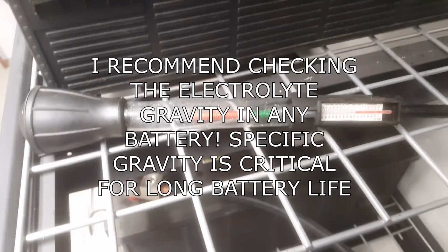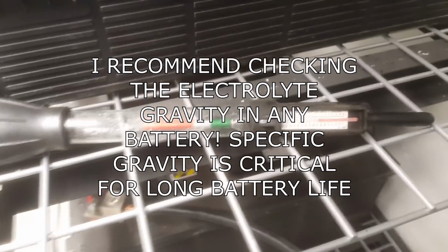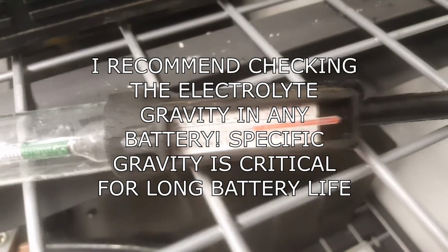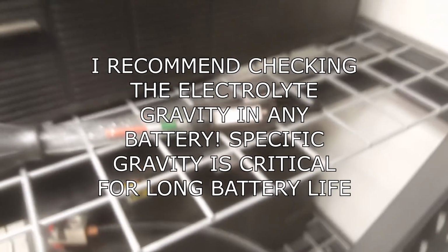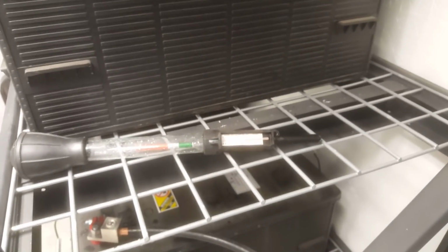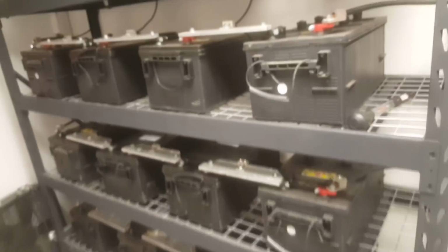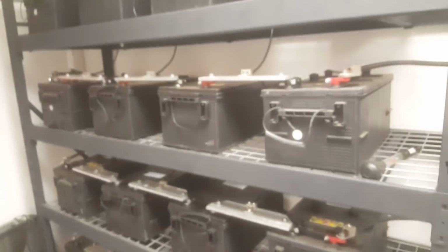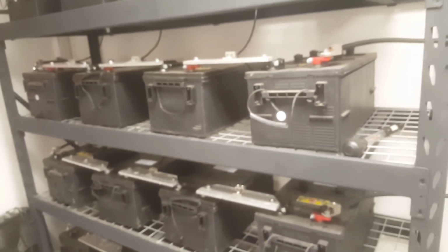If you're running off the grid, I strongly recommend one of these hydrometers that are temperature compensated. What this does is it gives you 2 things. It gives you the specific gravity of the electrolyte in the batteries, which is a very good indication of how charged they are. It also gives you a temperature of the electrolyte in the battery. So if one battery is having a problem, it'll oftentimes get hot, and you can better track what the status of the battery is based on cell temperature. So if all the batteries are, say, 70 degrees Fahrenheit and one cell is at 90 degrees Fahrenheit, you can better identify that battery has a problem.